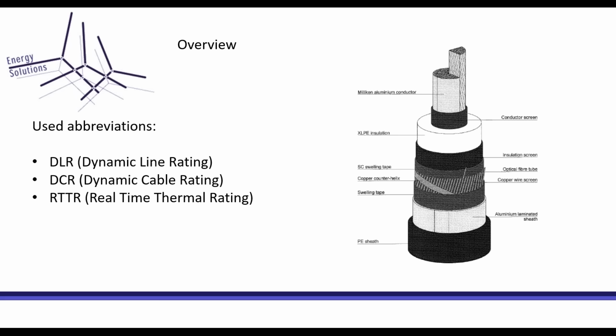Most commonly used is the term dynamic cable rating, also to make the difference with overhead lines. With overhead lines, you have a much different way of calculating dynamic rating capabilities compared to underground cables. With underground cables, you have a lot higher thermal capacitance of the surrounding soil, but also of the cable. And one of the challenges with designing new cable connections is that you cannot really know for sure the actual ampacity of the cable connection, because there are a lot of unknown parameters that can influence the rating of the cable. So the only way to really know the actual ampacity of the cable is to measure the temperature of the cable and perform calculations to verify the ampacity.